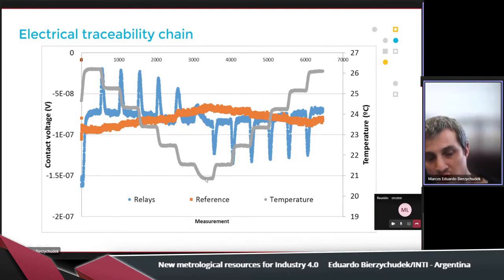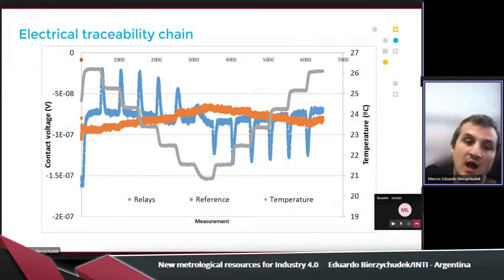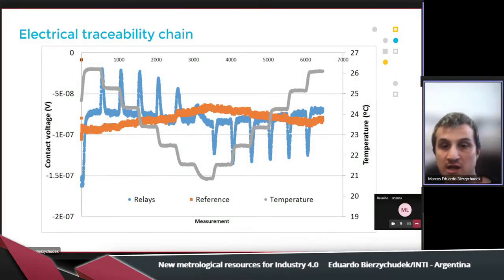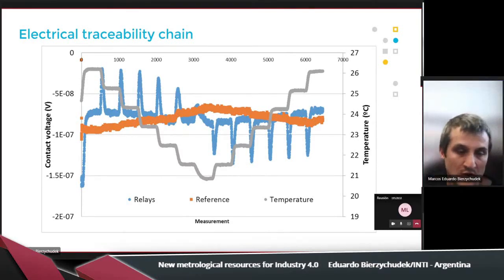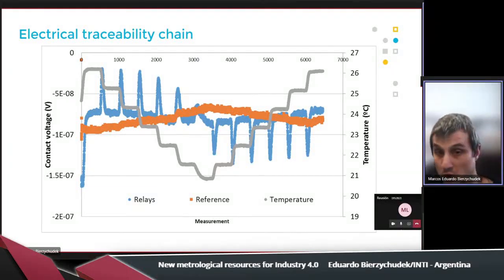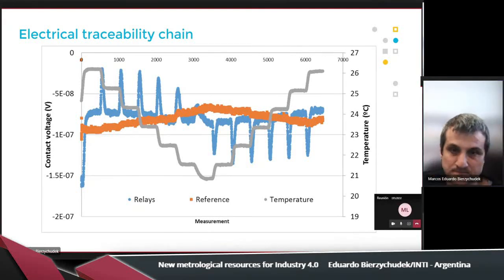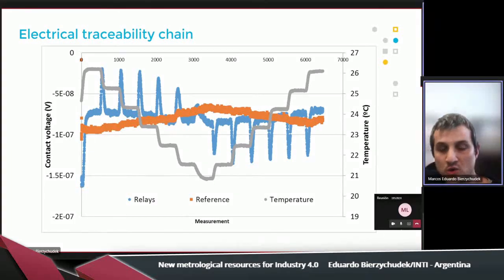You can see how the temperature was changed in the board, in a climate chamber, and then how, in blue, the thermoelectric voltage of one way of the board was always lower than 0.15 microvolt. The peak that you can see coincides with a change of the temperature, and this is produced because the gradient on the board increased the thermoelectric voltage. So with this measurement, we can be sure that the specification of a low thermoelectric voltage will be obtained if we maintain the temperature almost constant in the board.